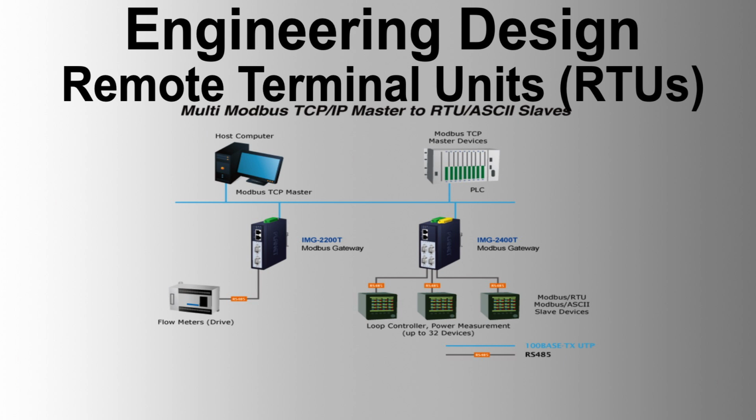RTU data logging. The RTU, Remote Terminal Unit, in the station control system has robust data logging capabilities designed to record and store critical data efficiently. Here are the key features and requirements for RTU data logging. Data logging capability. The RTU shall log any I/O or register data value. Each event log entry must be time-tagged with a resolution of 1 millisecond.